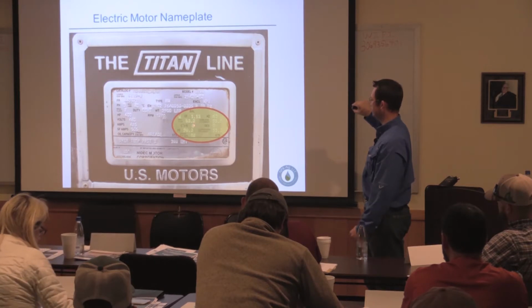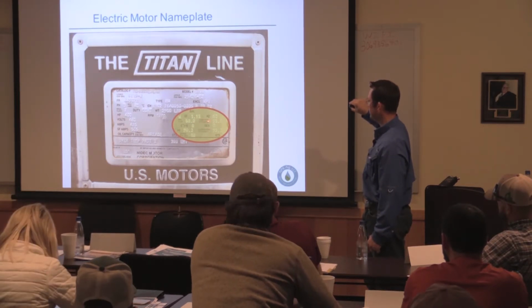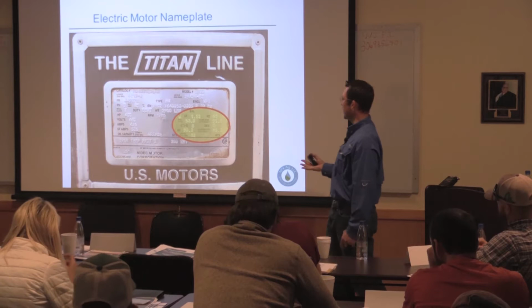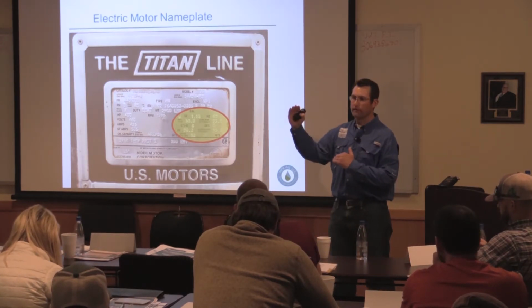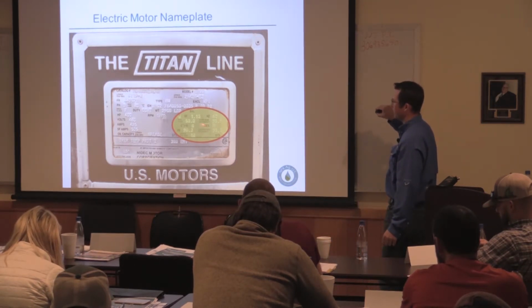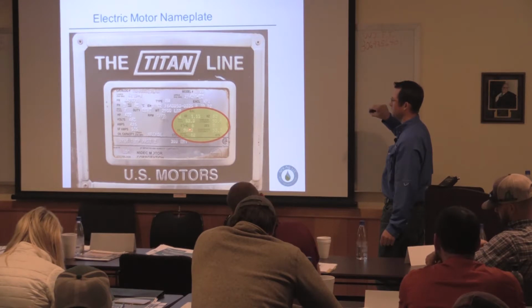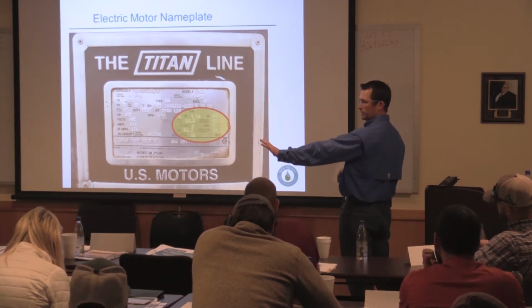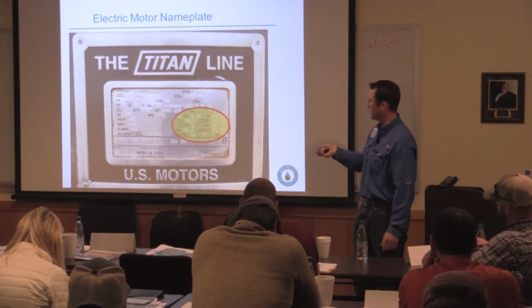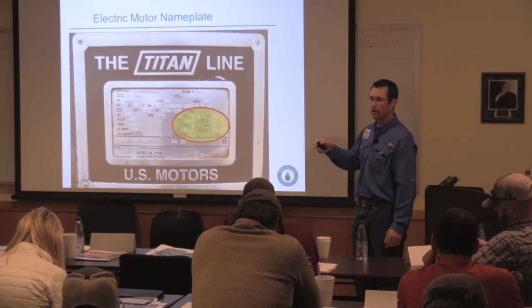The other thing you're going to look at is this service factor, that's how much you can overload it. The nominal NEMA efficiency of this particular motor, it's a big motor, so it's 95.8. I think Leon had showed it somewhere at 90%. Any more, they're all more efficient than that. Okay, the bigger you get, the more the efficiency is. They all will have a listed power factor also, and this is a worst case scenario. I've yet to see a motor in the field that was as bad as what their power factor said. Again, remember, this is the regenerative power that's sitting back to mess up the waves of the amps and the volts. This is the particular motor that when it was loaded on that previous genset was showing a power factor lagging of 93.